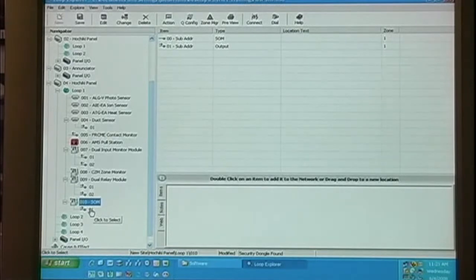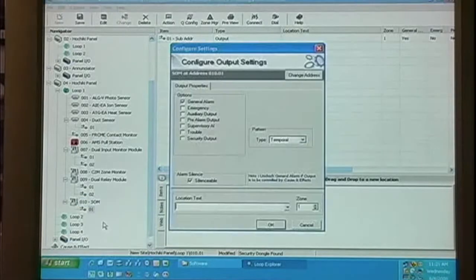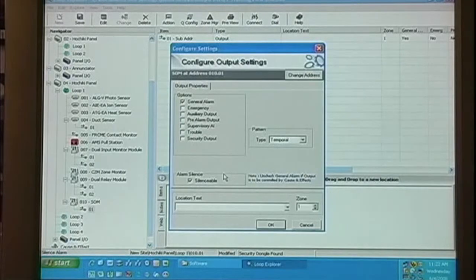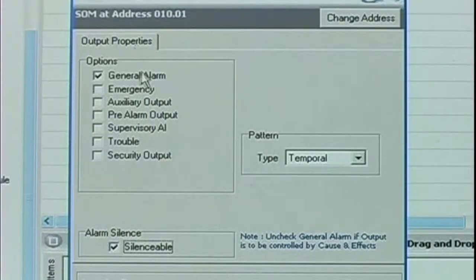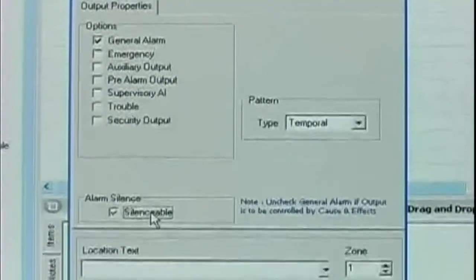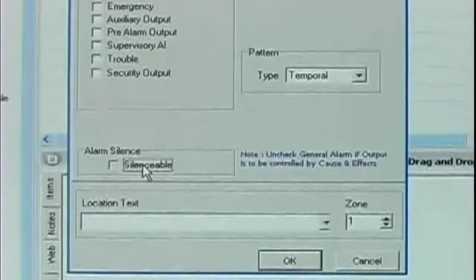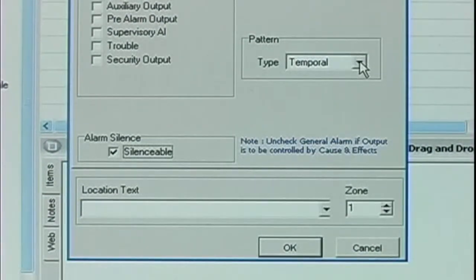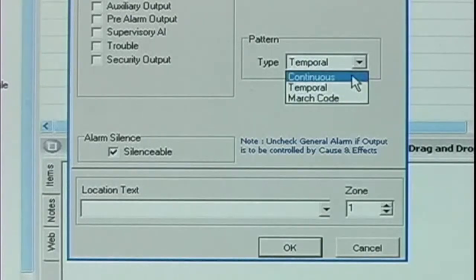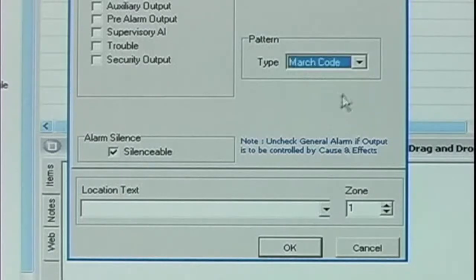When we go into the settings of the sub-address, you see it's very similar to the configure output settings of the R2M module. We have our general event options, we have our silenceable option, and we have our output pattern. The default output pattern is temporal, but we can choose continuous, temporal, or march code for our SOM output.